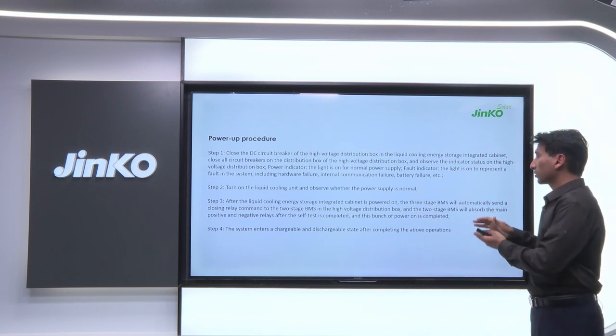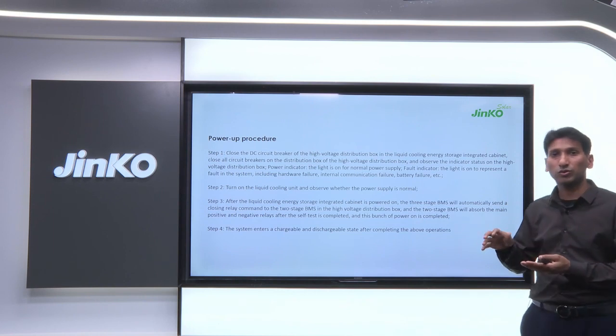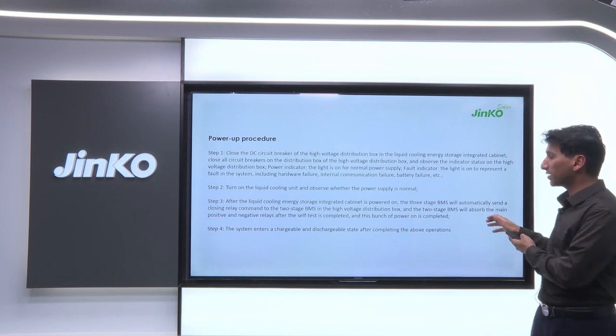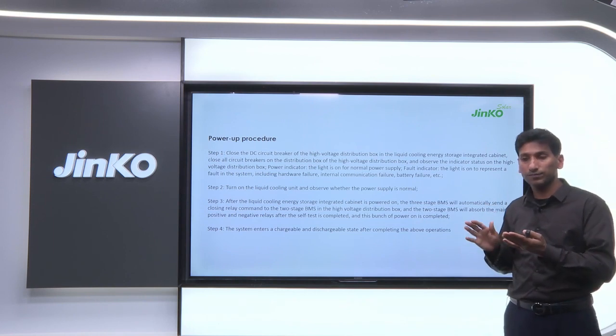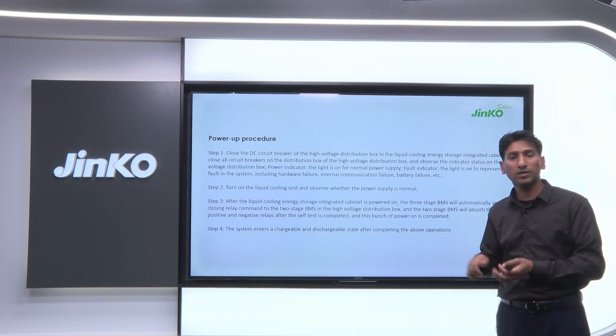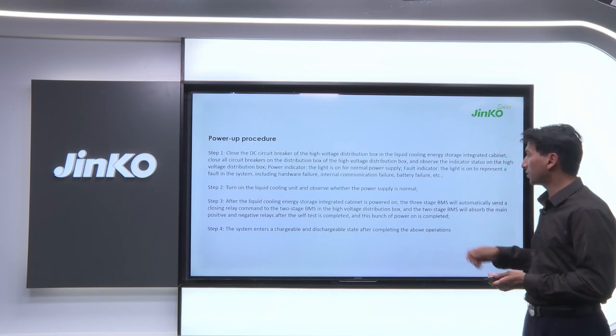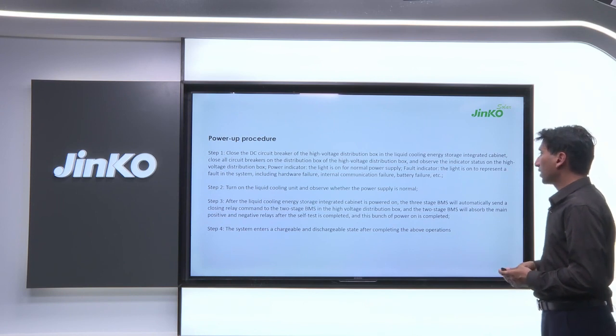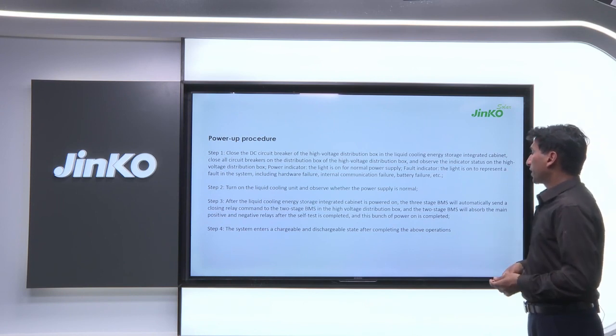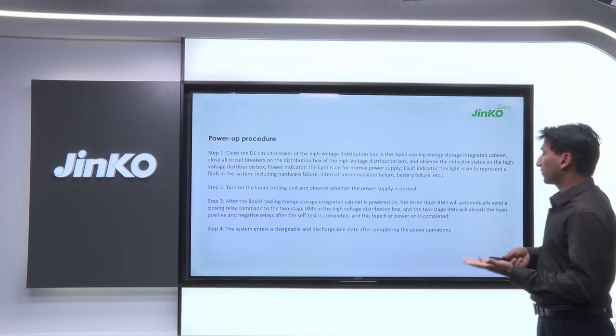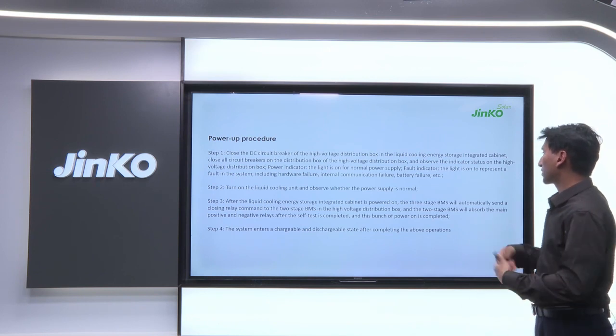Then you move to the liquid cooling system. You switch it on, and then you move to the PCS side, and there's an AC switch there. There's a circuit breaker there. You switch on that circuit breaker. After the liquid cooling energy storage integrated cabinet is powered on, okay, now you have done everything. Now the system is powered on.